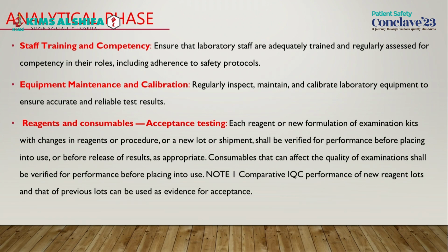He has to provide what is the volume of the calibrator, what is the content of the calibrator, what is the acceptable CV range for that particular parameter as per the manufacturer's guideline, and then also for our own CLIA guideline. So that is how we have to ensure that the equipments are maintained, and unless the equipment is well calibrated and properly maintained, it will give a lot of erroneous results.